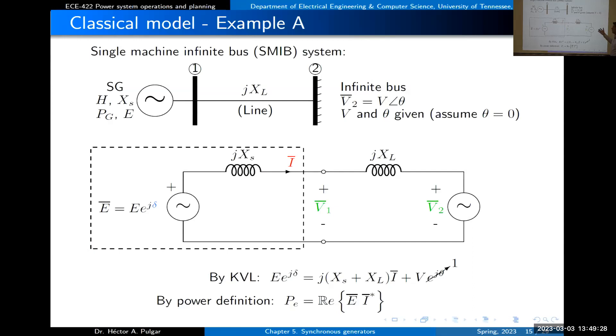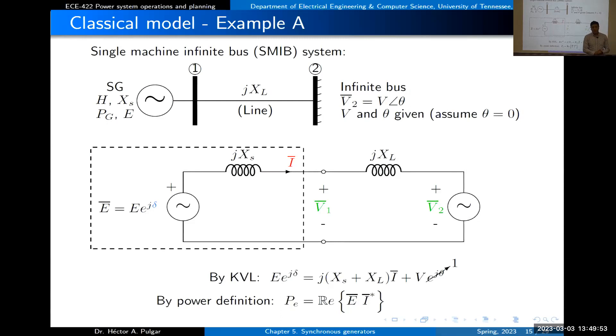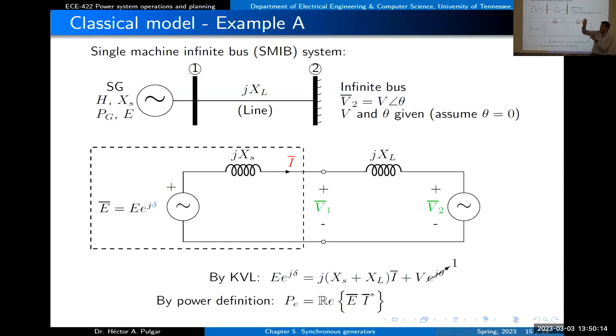We were talking about this very simple system with one synchronous generator. Last class we covered two important concepts: inertia and the angle delta. Inertia describes the grid's resistance to frequency oscillations. The generator has inertia H, defined as half the time to take the machine from rest to nominal speed — mathematically, it's the kinetic energy stored at nominal speed divided by the nominal power.